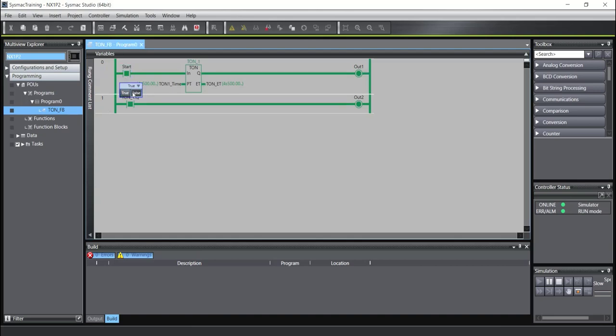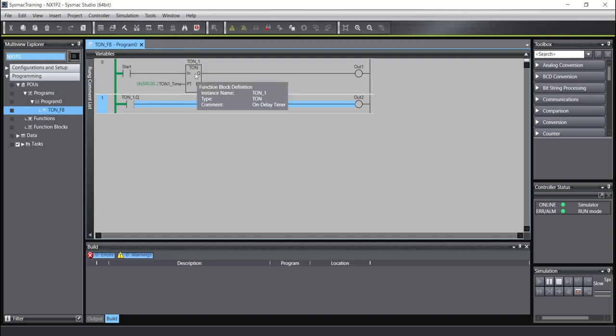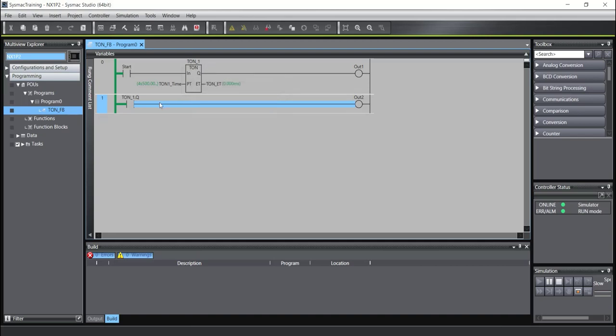And when I turn off the input, the output will be turned off. And also you must know you cannot use the same name for two function blocks. When you write here TON_1, you cannot use this name for another function block.